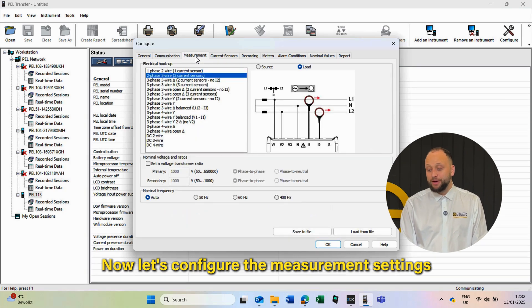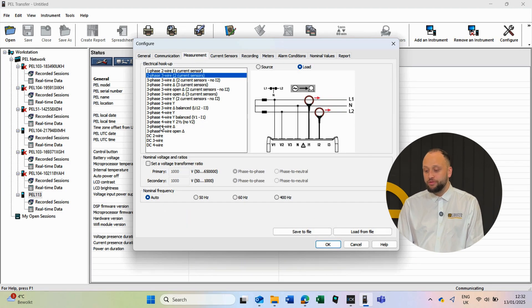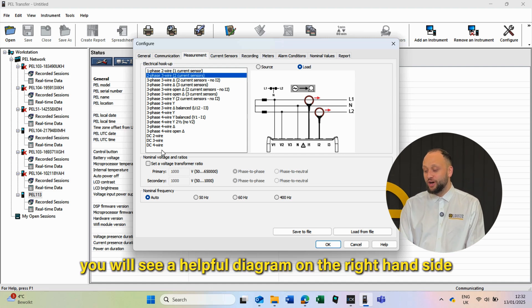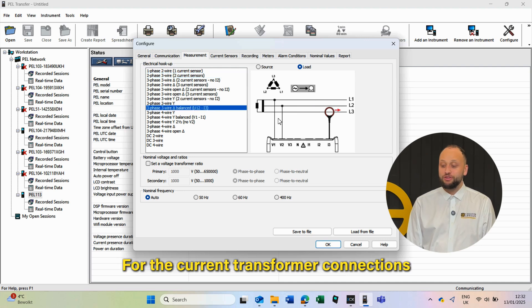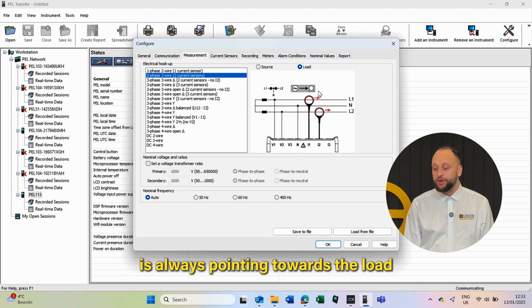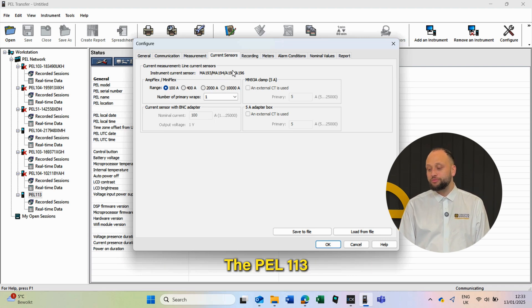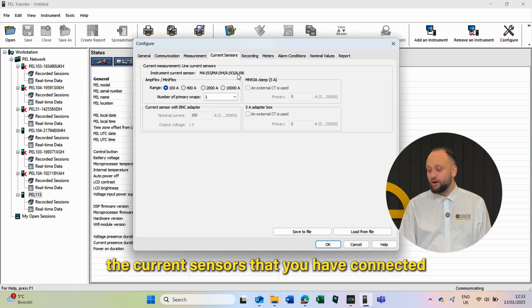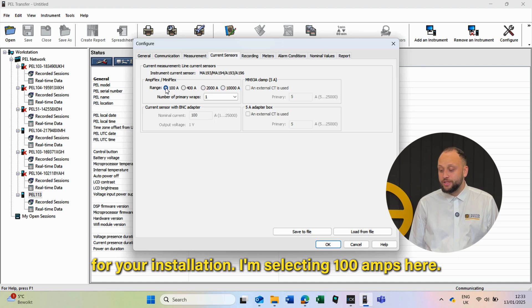Now let's configure the measurement settings so you can choose what type of electrical installation you're working with. You will see a helpful diagram on the right-hand side showing you how to connect the PEL to the voltage and current sensors. For the current transformer connections, make sure that the arrows on the CT are always pointing towards the load as shown in the diagram — this ensures correct measurements. The PEL 113 will automatically detect the current sensors you have connected; you just need to choose the correct current range for your installation. I'm selecting 100 amps here.